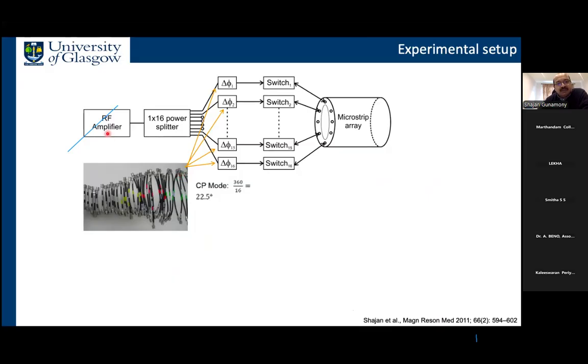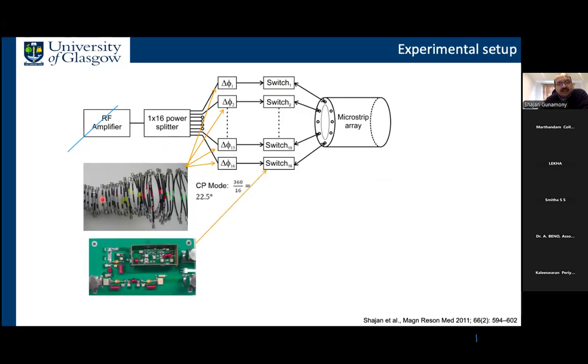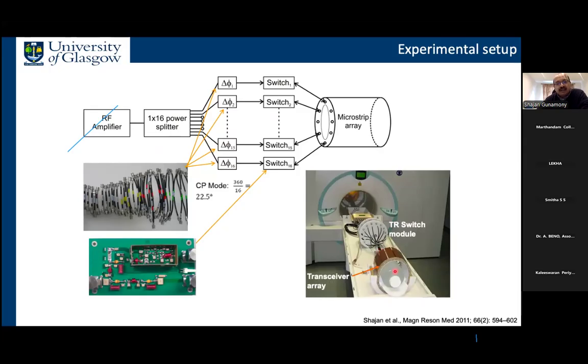So this is the setup. We have a single amplifier. Because it's a 16-channel coil, you need a 16-channel power splitter, or 1/16 power splitter. The output from the splitter is fed through this TR switch circuit, which is here. Then we can connect different coaxial cables and change the phase length, or the phase of the current to each of these coil elements. And this is the complete setup. So we have a 16-channel array coil, a TR switch module with 16 channels, and a power splitter, and there's a cable in between whose length we can alter to change the phase.